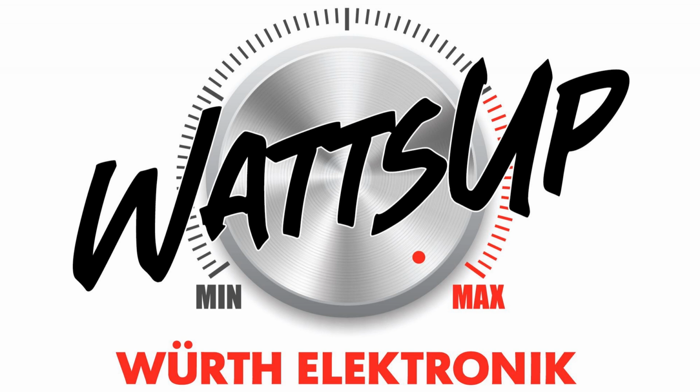The sectional winding has the advantage of a higher rated voltage, because the wires are simply further apart from each other. So insulation is not that critical, and we can reach higher rated voltages. But on the opposite side, the stray inductance is higher, because the further apart the windings are, the smaller the coupling, and the higher the stray inductance. So it can go up to 5% at maximum.